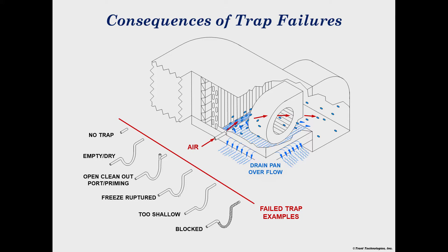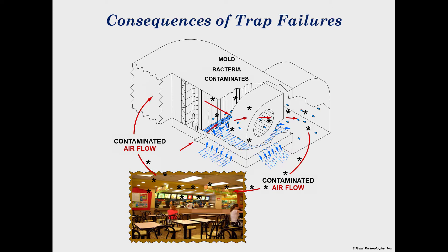These events cause damage to the air handler and the building, creating a perpetual internal wetness, a fertile growth place for mold, bacteria, and other health-threatening biological contaminants. The property damage and maintenance effort required for this type of system eliminates any hope for low life cycle cost. Furthermore, since all the air inside a building may pass through the contaminated air handler several times per hour, health-threatening conditions are virtually certain. Thus, the use of systems equipped with condensate traps in reality rules out the realization of low HVAC operating costs in healthy building environments.